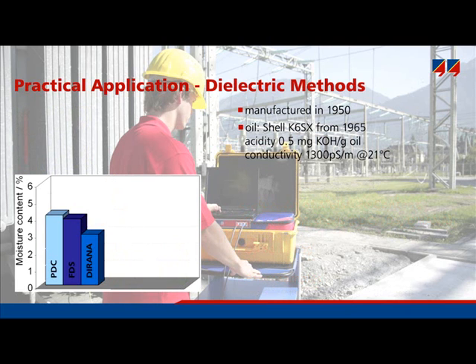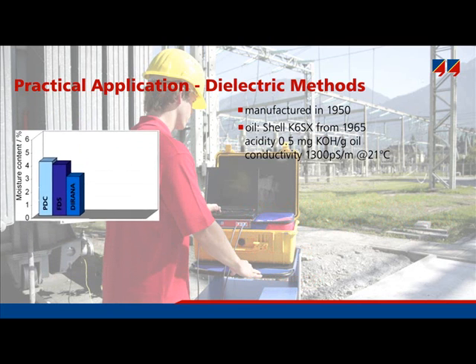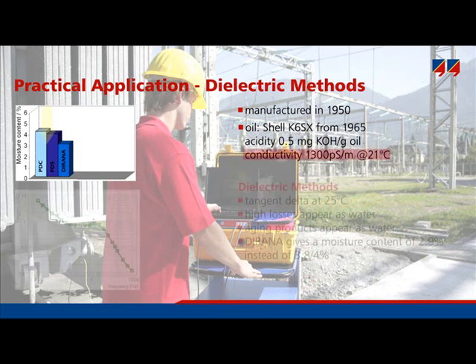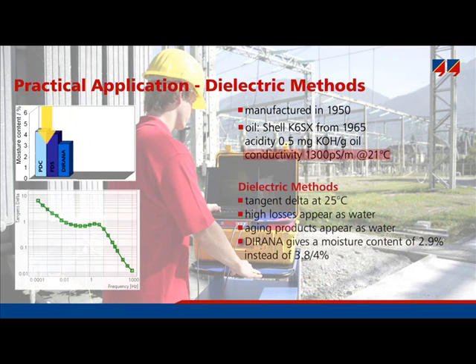How can such contradictory results be explained? Starting with the dielectric response measurement, the high conductivity of the oil suggests that a lot of conductive products resulting from the aging process are dissolved in the oil and hence will be deposited in the cellulose insulation. If the analysis software does not compensate for these aging products, it will give a value for the moisture content which is too high. This is the case for typical software provided with PDC and FDS measuring devices.